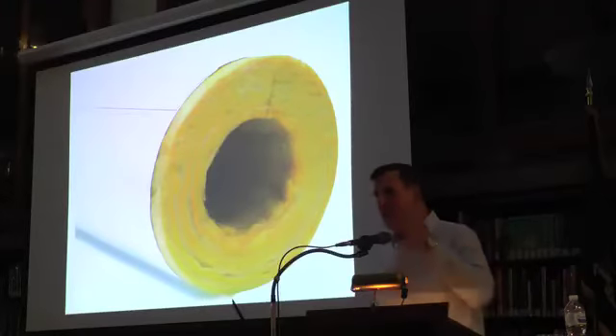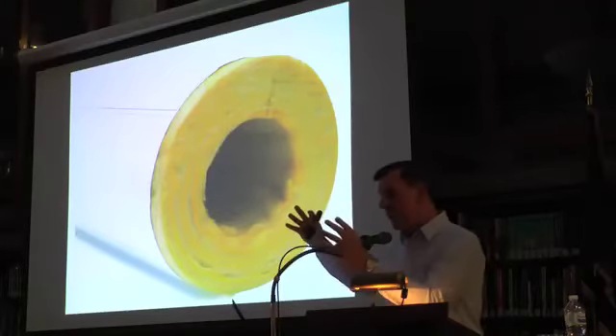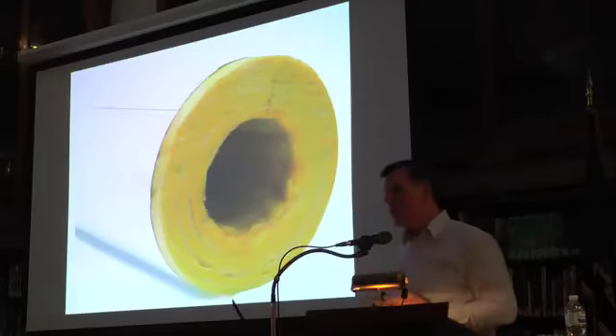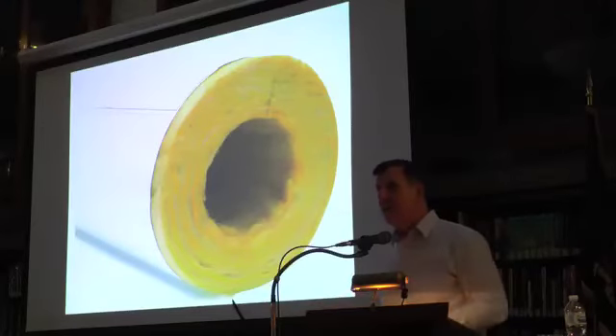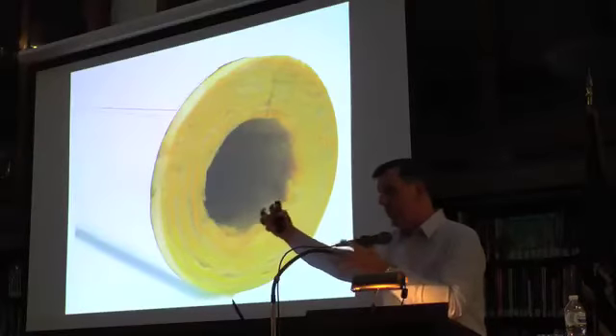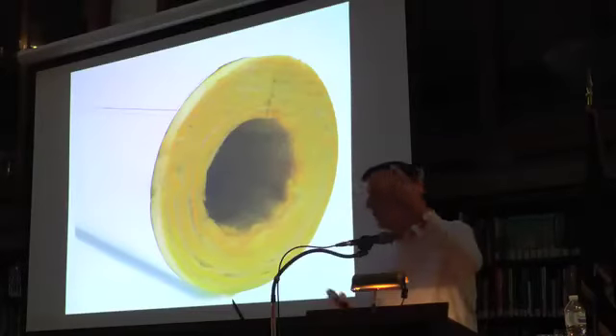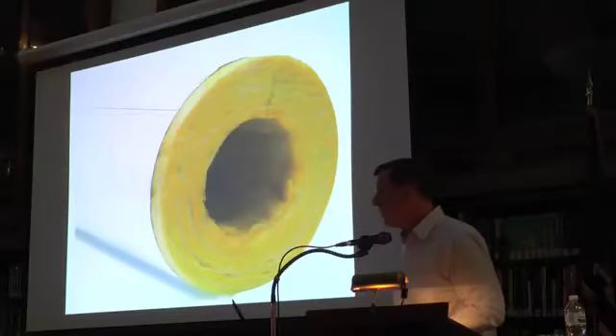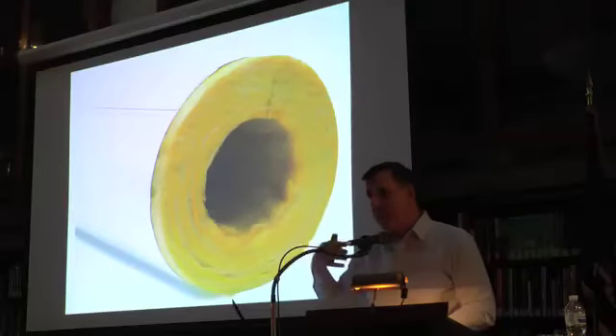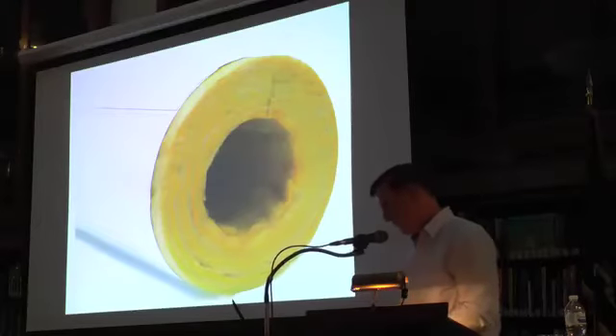Think about this. If you've got a million BTU boiler in a building with 1 million BTUs worth of radiation, that includes insulated pipes. And you remove the insulation, suddenly the load on the pipes goes up by 5 times. Suddenly you've got a 1,000,000 BTU boiler with maybe 1.25 million BTU worth of stuff that can condense steam. And the steam doesn't care. The steam just goes out and it turns into water on anything that's cold. And you wonder why it's not getting hot at the end. You see? All you've got to do is put the asbestos back on and things go back to the way they were supposed to be. So, a lot of things we learn as we go along.